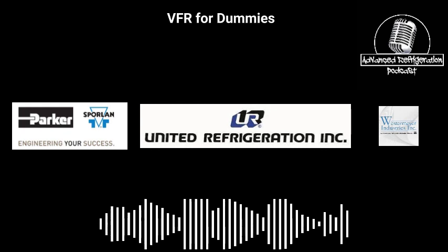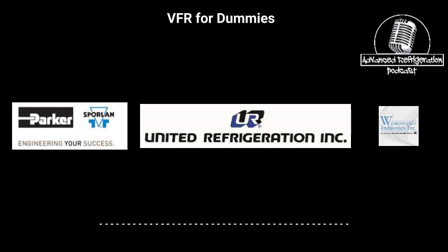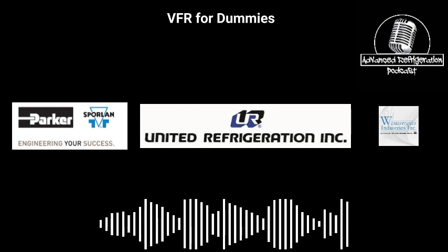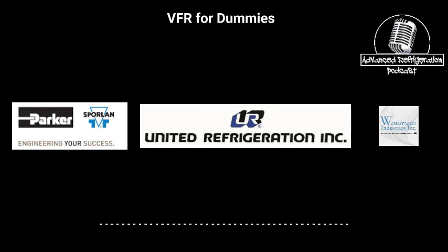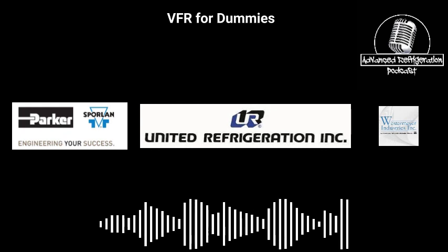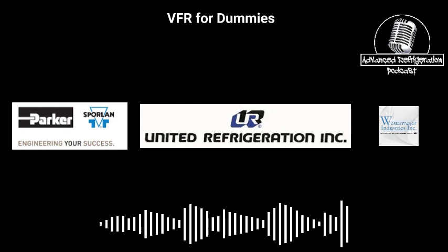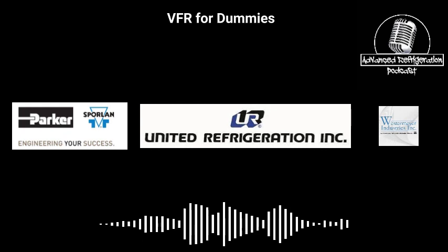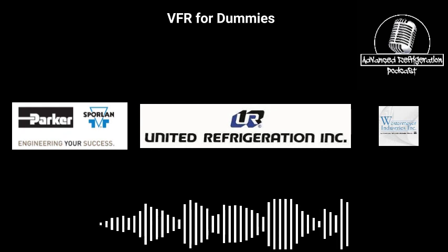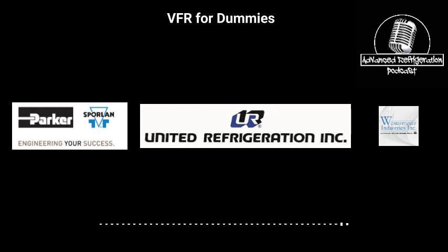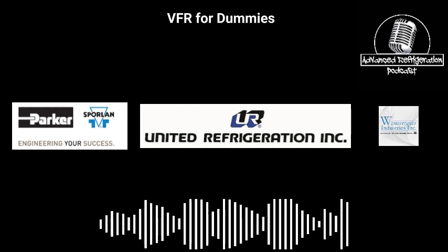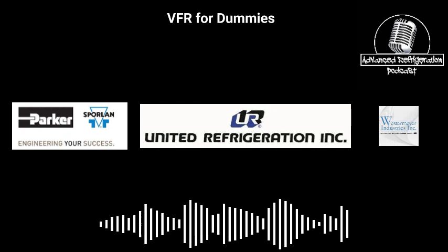No, you guys get a lot of electrical part failures, like boards and. If you know anything about Northern California, our power grid is junk. During the summertime, our utility floats the carrier voltage about 500 to 505 volts. Ooh. Our machines are rated 460, 10% tolerance. So we're at or above tolerance for most of the summer. And yeah, they call it a thermal event. It's not an explosion. It's a thermal event.